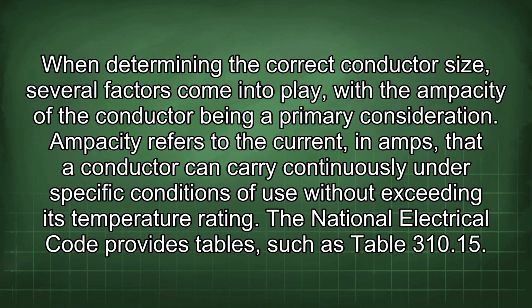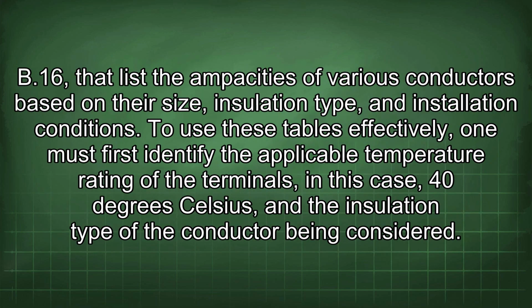When determining the correct conductor size, several factors come into play, with the ampacity of the conductor being a primary consideration. Ampacity refers to the current, in amps, that a conductor can carry continuously under specific conditions of use without exceeding its temperature rating. The National Electrical Code provides tables, such as Table 310.15(B)(16), that list the ampacities of various conductors based on their size, insulation type, and installation conditions.